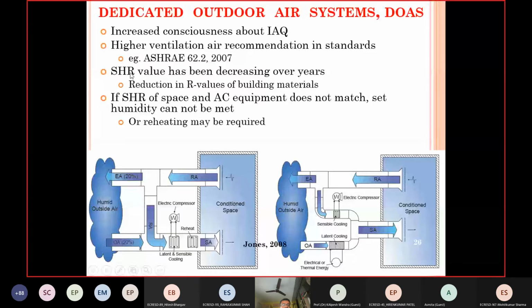And again, what is happening is that over a period of time, as we improve the building envelope and reduce the penetration of heat into the buildings, the sensible heat ratio value will go on decreasing. It means that the latent heat portion, the latent heat removal ratio, is becoming higher, and because of that, you have to address the humidity part separately. Okay.